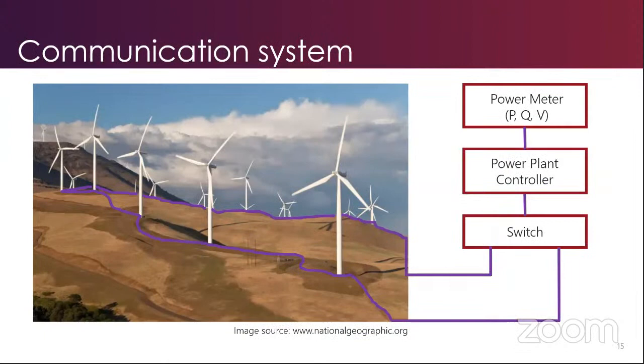Communication systems are an important part in battery, solar and wind systems. As shown in this diagram, there can be a number of turbines in a wind farm, but the whole thing is controlled as one system held together by a communication network, shown here with purple lines. This communication system carries targets or operation instructions to the turbines and carries operational data back to the plant controller. The network is typically connected via switches or other communication devices feeding into the main controller, called the plant controller or site controller. It sends commands to the turbines and reads data back from them for operational purposes.